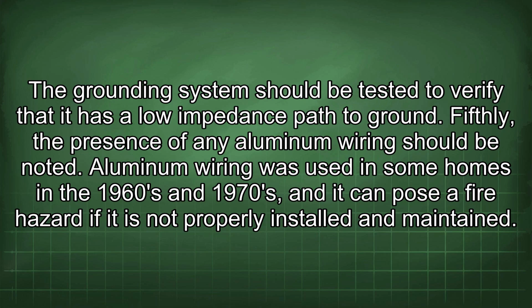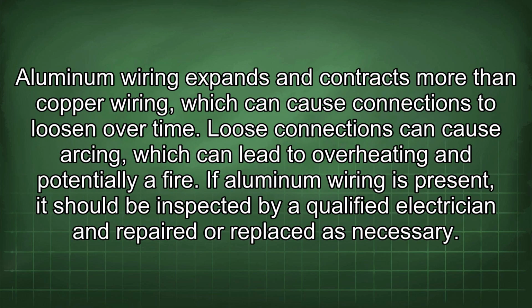Fifthly, the presence of any aluminum wiring should be noted. Aluminum wiring was used in some homes in the 1960s and 1970s, and it can pose a fire hazard if it is not properly installed and maintained. Aluminum wiring expands and contracts more than copper wiring, which can cause connections to loosen over time. Loose connections can cause arcing, which can lead to overheating and potentially a fire. If aluminum wiring is present, it should be inspected by a qualified electrician and repaired or replaced as necessary.